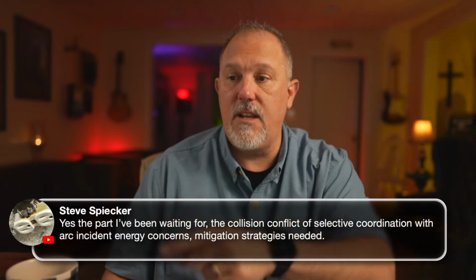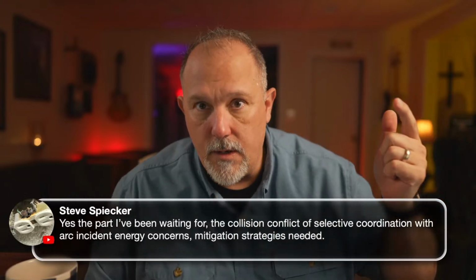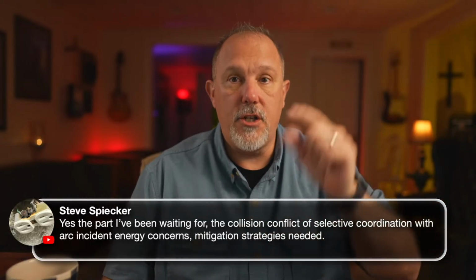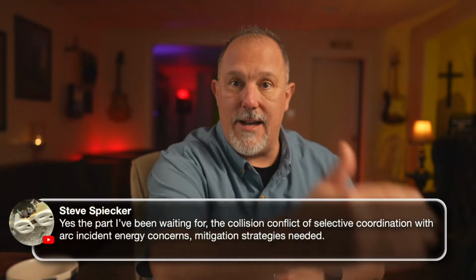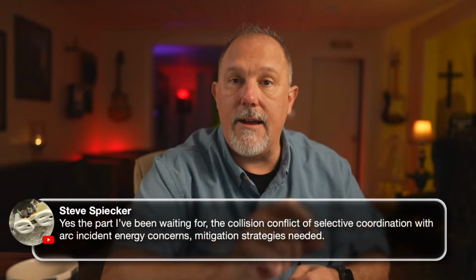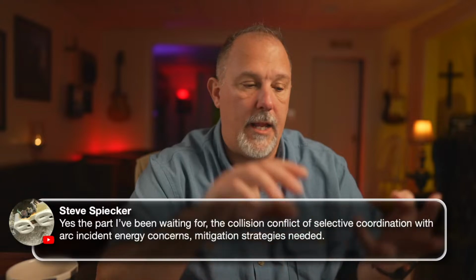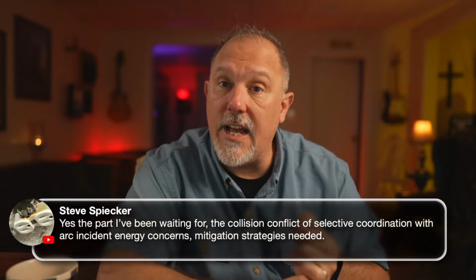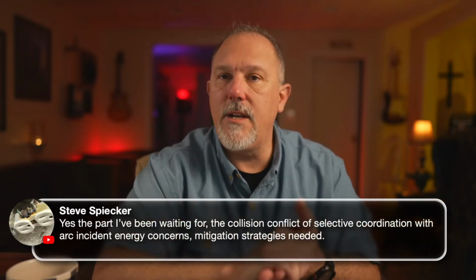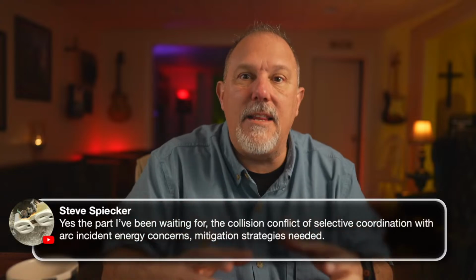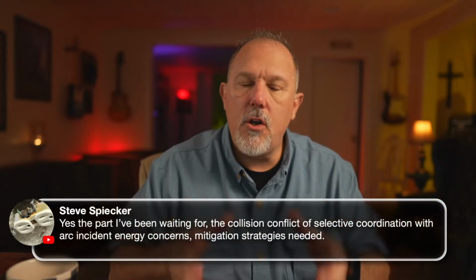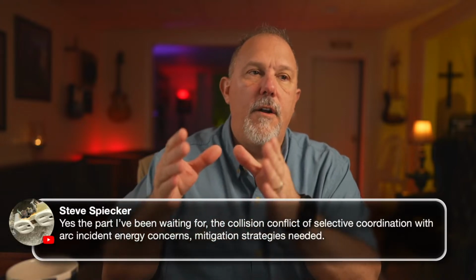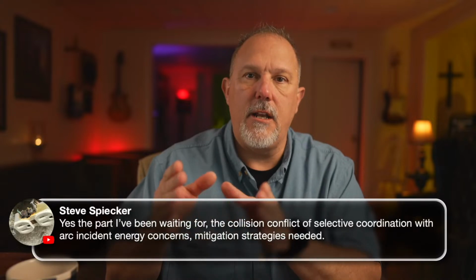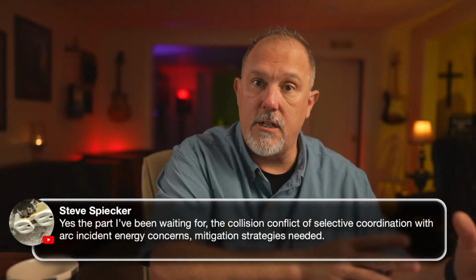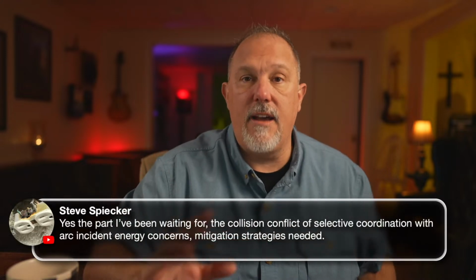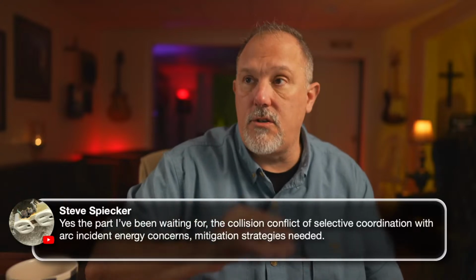In fact, Nihad El-Sharif and I are working on a paper for IEEE that shows when you have a design goal of selective coordination, I can address the incident energy through a lot of different technologies. You've got zone selective interlocking, differential relaying, arc reduction maintenance switch, active arc flash mitigation systems. And if you don't want to do any of those, you can do an arc resistant piece of equipment and at least contain the arc flash and vent it out. So there are so many solutions on the table to address the incident energy concerns that I can achieve selective coordination, and I can minimize the damage to my equipment.